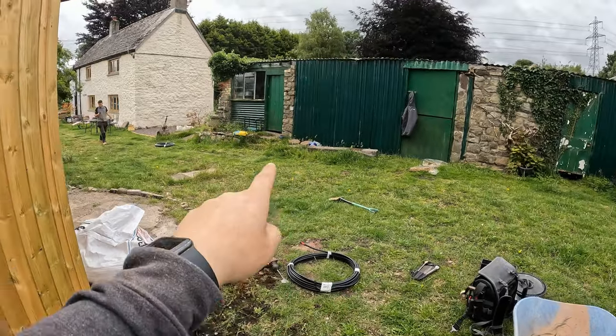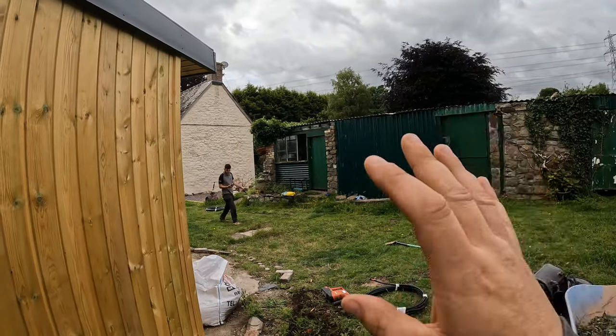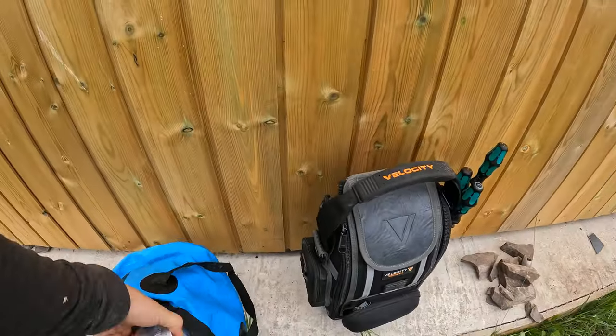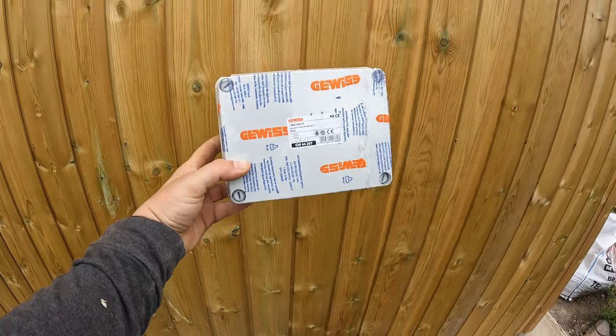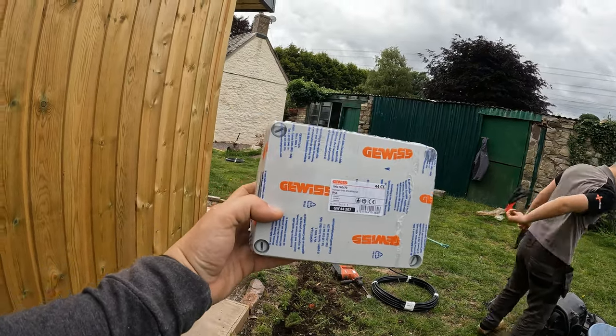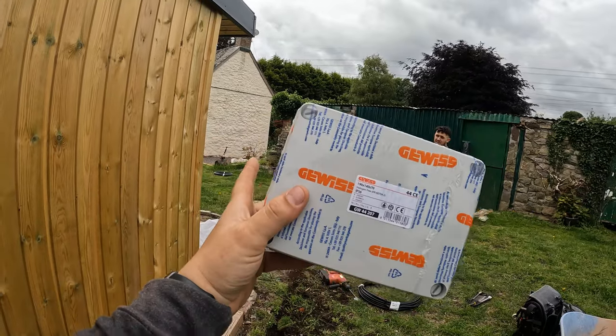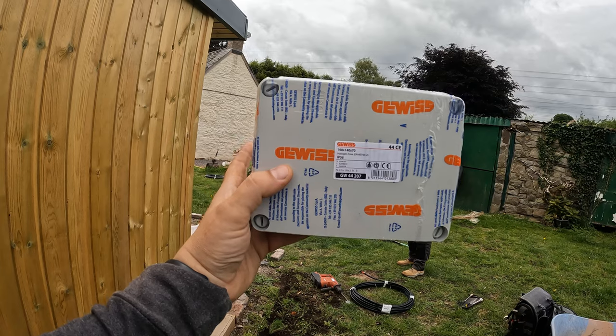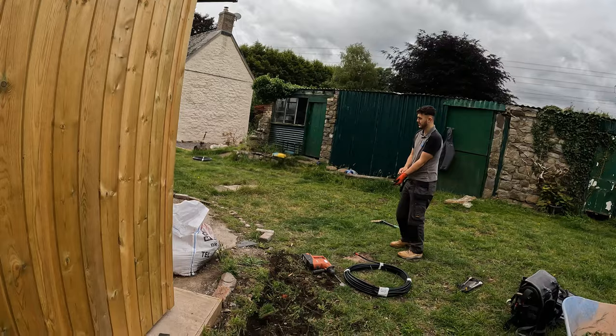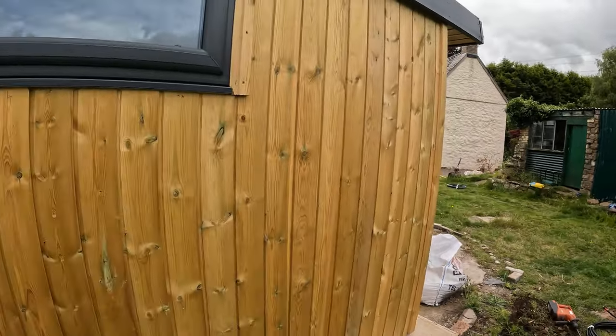We have a 6mm from the consumer unit to here. The 16mm and the 6mm are going to be joined in a Gewiss box, and we're going to derate it to 32 amp for now. When it's all knocked down, we'll put in a four-way consumer unit and up it to a 63 amp MCB to feed the shed — we can then split into separate circuits: hot tub, sockets, and lights.